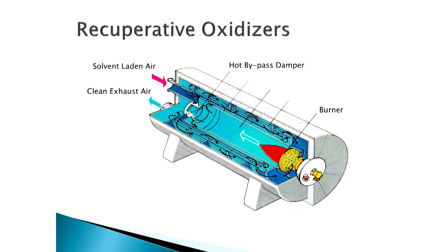In its simplest schematic form, it's a burner and a combustion chamber, and we either bring the gases in and pass them on the outside of the heat exchanger tubes before going through the burner, and then the outlet gases go through the inside of the tubes, or we can design them in reverse. We'll do that either way depending on whether in the combustion process there are any byproducts of combustion. So in the case where we're seeing a lot of siloxanes and so forth, we may want to have the exhaust gases pass through the tubes so that you can go in and ream the silicon dioxide and so forth out on a best practices maintenance basis.